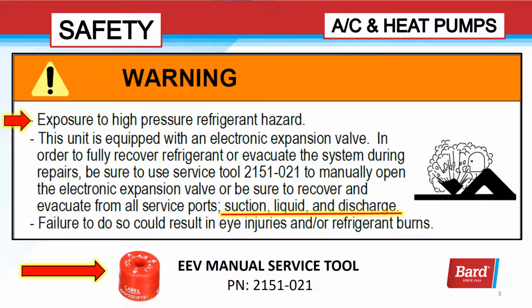Warning: there is an exposure risk to high-pressure refrigerant unless you follow these steps. This unit is equipped with an electronic expansion valve. In order to fully recover refrigerant or evacuate the system during repairs, we need to make sure that the valve is open. Use the service tool, part number 2151-021, and you can use this to manually open the EEV.